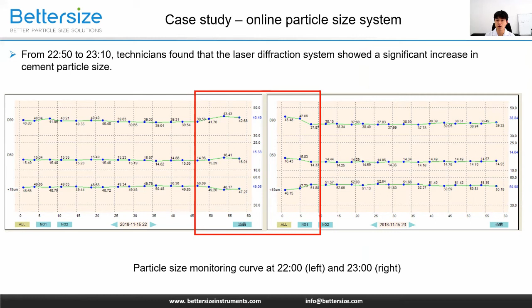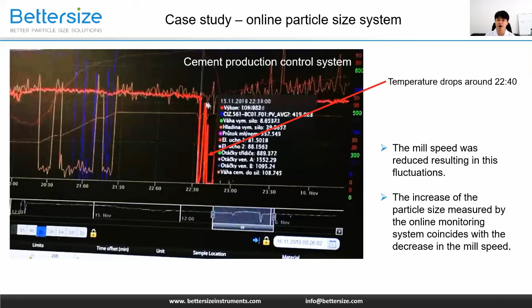to 11 p.m. At the same time, the temperature control curve of its overall control room showed there were drops and fluctuations around 22:40. After the technicians conducted investigation, they confirmed that the mill speed was reduced at that time. So the increase of the particle size measured by the online monitoring system coincides with the decrease in the mill speed. By the way, during more than 5 months of use, Lafarge has carried out only 2 maintenance of the instrument, which was to clean the measuring area. So the maintenance cycle and instrument reliability are far beyond user expectations.